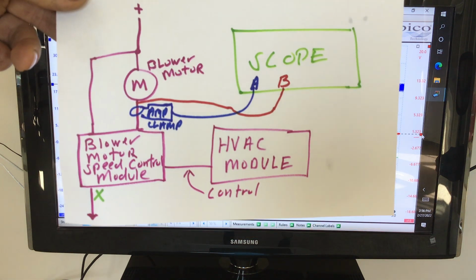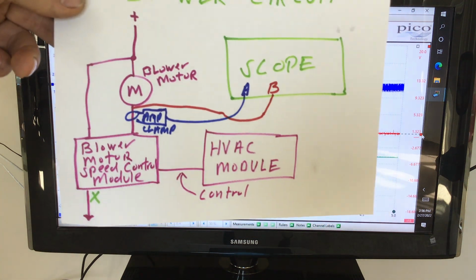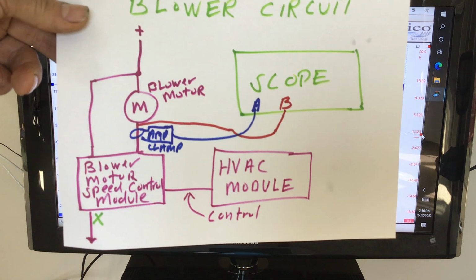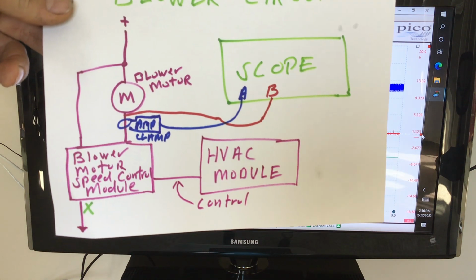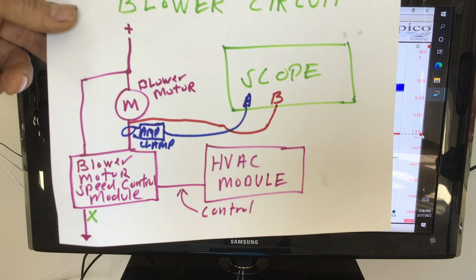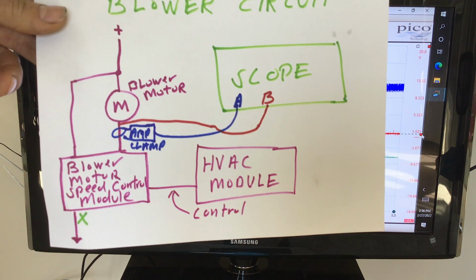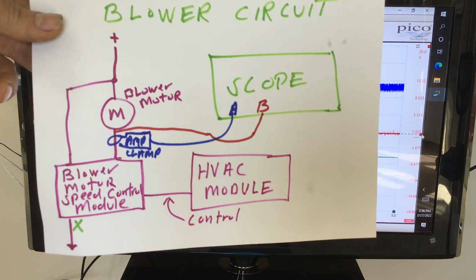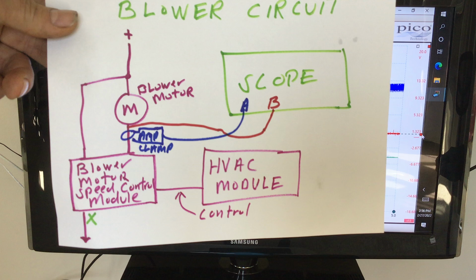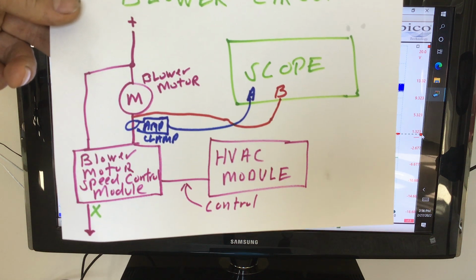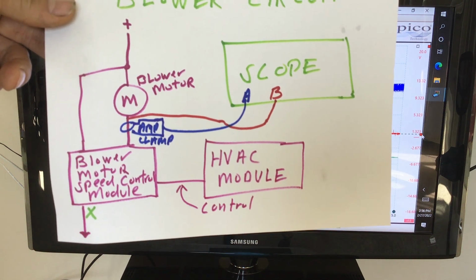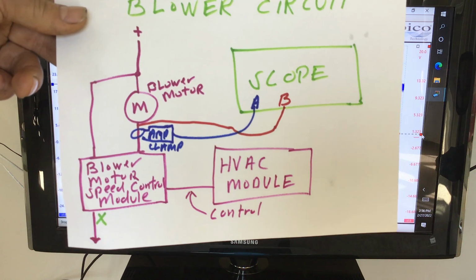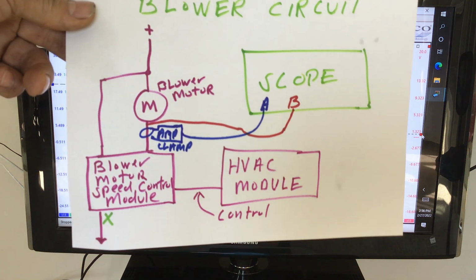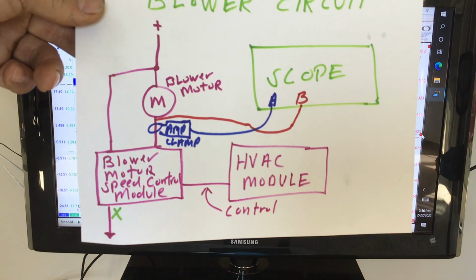So we're hooked up on two channels on the scope. Channel A is an amp clamp—I don't know if it's on the ground side or hot side of the blower motor, but it doesn't matter since it's measuring current flow. Channel B is on the ground side of the blower motor itself, not the feed side. Take a screenshot of that and then we'll look at what's going on.